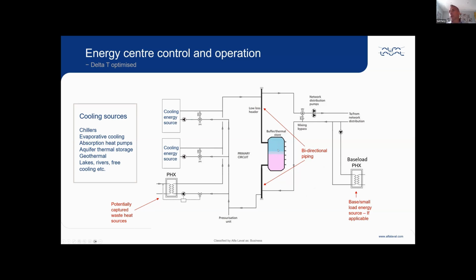And again, you probably wouldn't do anything for a while and then start to switch off certainly the less efficient sources or the most carbon intense sources as that comes down. And obviously your waste heat or your free cooling, you leave that running as much as you possibly can. So that's how you would typically optimize the use of the energy sources based on their carbon implication and their cost as well, of course.